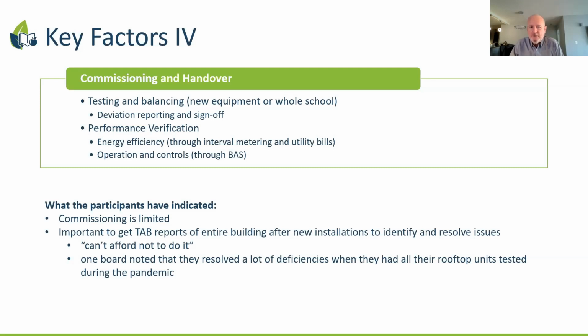The other big area was performance verification, looking at energy use. Who does that? Who's going to take care of that on a go-forward basis? Looking at the energy side through interval metering and utility bills, and looking at operation and controls through the building automation system. If we don't check it once it's just been built, and the designers and commissioning agents have gone, how are we going to fix it after the fact?